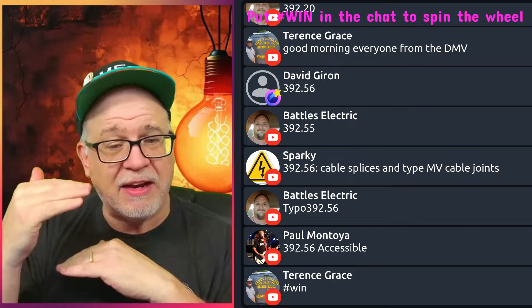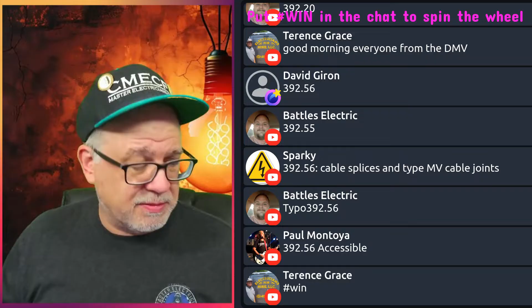The code allows you to make this as long as those splices are accessible, okay? And they are allowed to protrude above the side rail because maybe it's a bigger splice, as long as none of that is subject to physical damage. And it may or may not be. I can't speak for every installation, okay? But I would say 99% of the time, wherever I'm going to install a nice, adequately done cable tray, it's not going to be subject to physical damage. I would go out on a limb and say that most of the time.